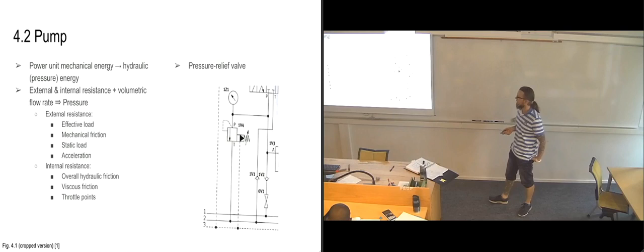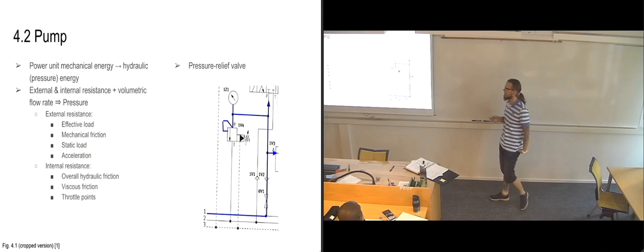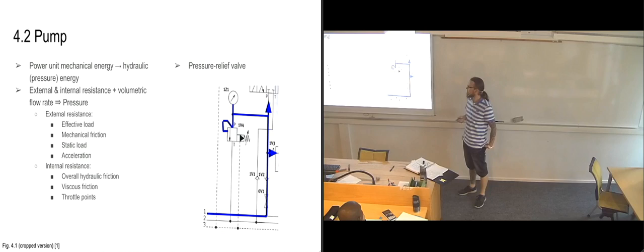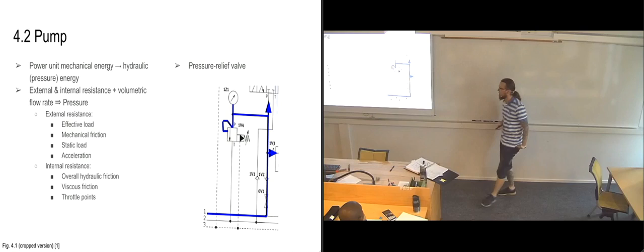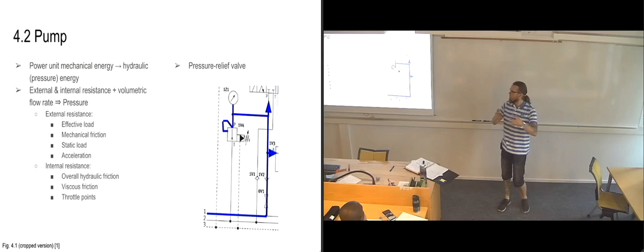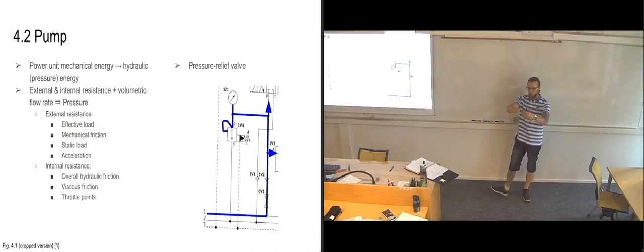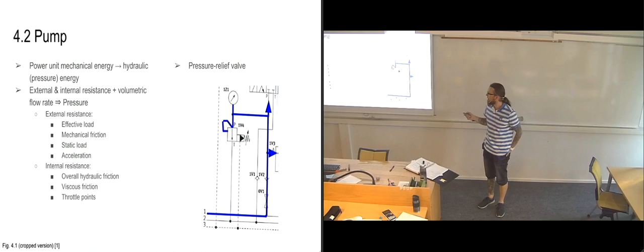So when we have pressure coming in here, it's going into the system, it's going up to the pressure gauge, and we have pressure pushing on this valve. If we now increase our pressure a bit, so there becomes more pressure inside our system, it's now too much, the pressure gauge is pointing too high, then this arrow moves over into the correct position. So this is actual mechanical components inside the valve that are being pushed into position. So it's not just an arrow on the symbol, it's actually opening up flow to allow the flow through there. So then we get a return line here.